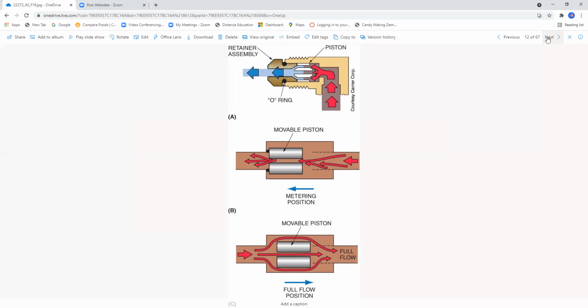Now, these things are different from the indoor coil to the outdoor coil. Please remember, you're typically going to have two metering devices, and if they have this check valve design feature, do not interchange the indoor with the outdoor piston. They are very specific. So if we have the flow of refrigerant, in this case hot gas, going through here, notice that the piston is allowing for the full flow in this position. Now in the metering position, we're blocking off the flow of refrigerant and we are metering. So this thing is a dual function piston. We can use it as a check valve in one position and as a metering device in the other. These are very common out there.